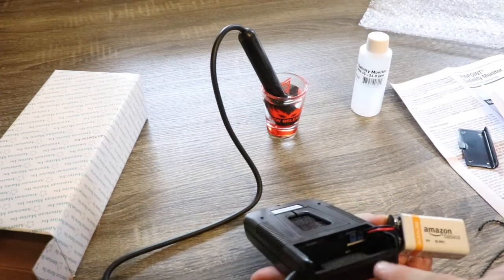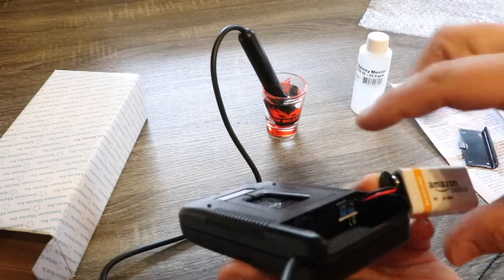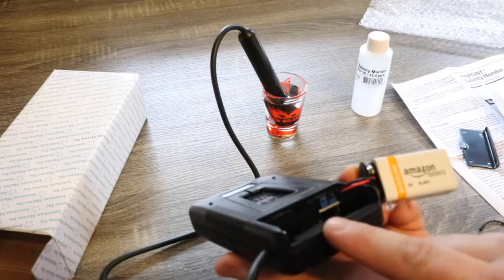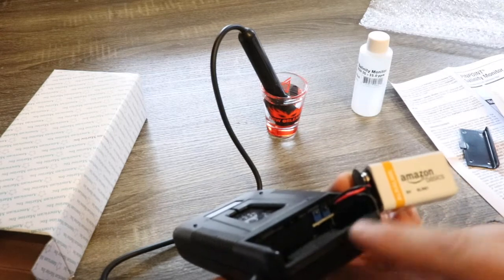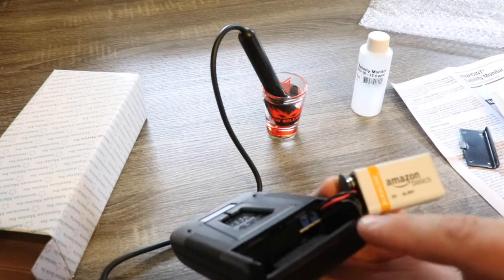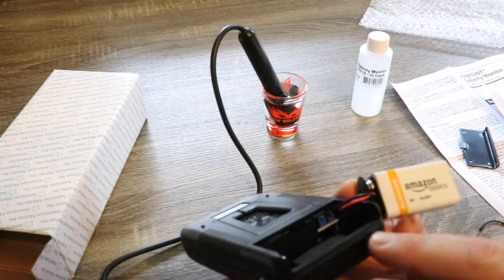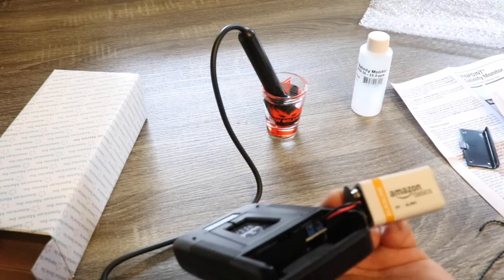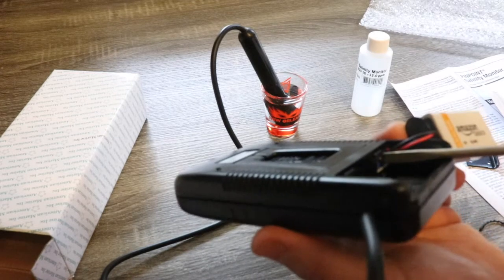Now there's two screws that you can see just barely in the blue there. The one closest to the center is the one that you adjust to make your monitor calibrated. The one furthest to the outside is the factory screw. Do not adjust that. That was set by the folks at the factory and it doesn't need to be adjusted at any point.